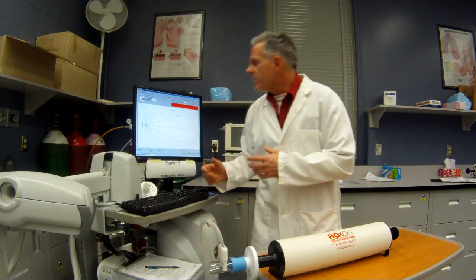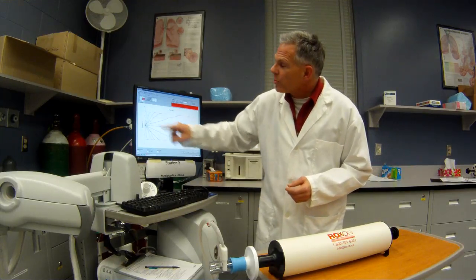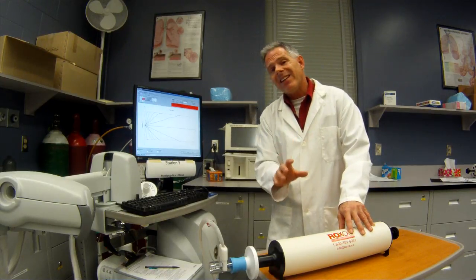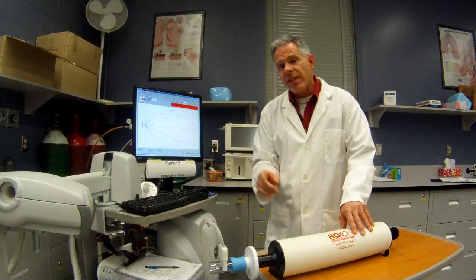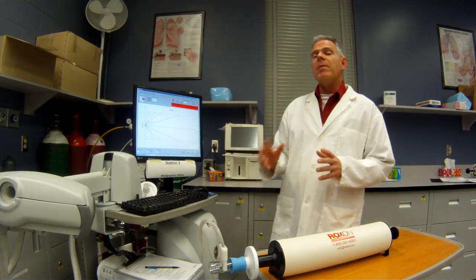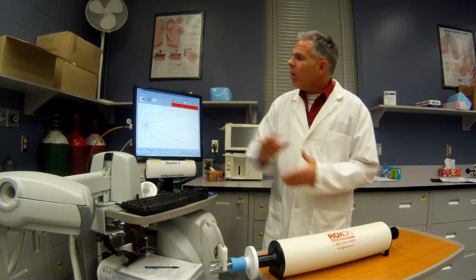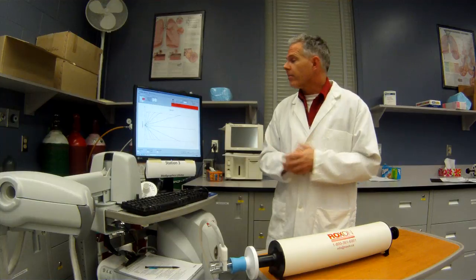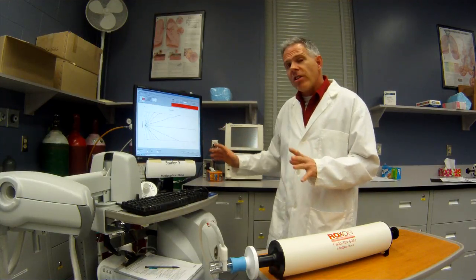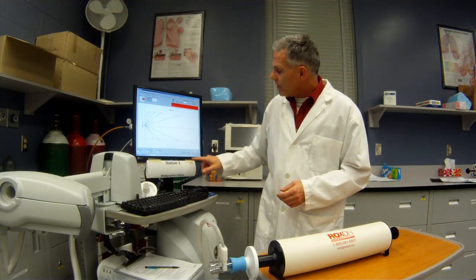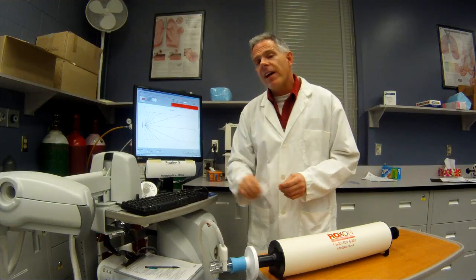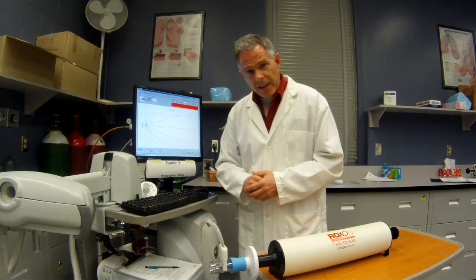Okay? But we repeat this a couple of times until this comes in and was measuring exactly the 3 liters as we need. Okay? It's important that it meet ATS criteria, and that's plus or minus 3%. So on a 3-liter syringe, that's 90 mL. That's actually quite a bit. You'll find out that these devices calibrate much closer than that. In fact, these ones calibrate to within less than 1% error. So that's basically an orientation to the device and how you calibrate. You might have to repeat this a couple of times until you get a calibration pass. Then we print up the report, and you'd sign it off as being calibrated and verified, ready for use for the day. Thank you very much.